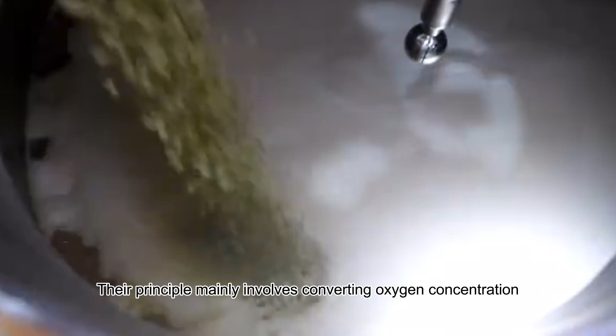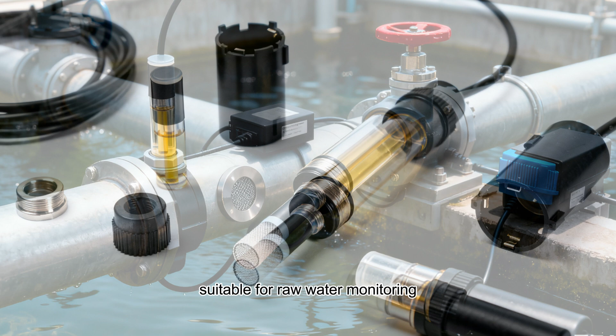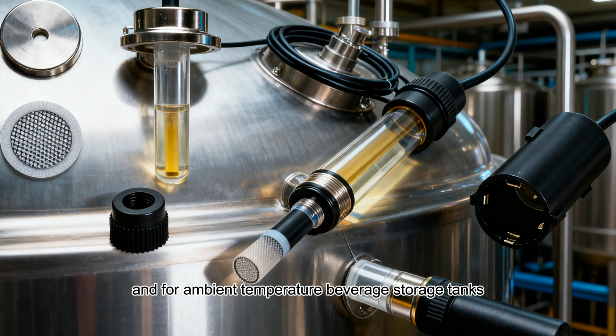Polarographic dissolved oxygen sensor: a redox reaction occurs at the probe cathode, generating a current whose magnitude is directly proportional to the dissolved oxygen level. Suitable for raw water monitoring where high accuracy is not required, and for ambient temperature beverage storage tanks.